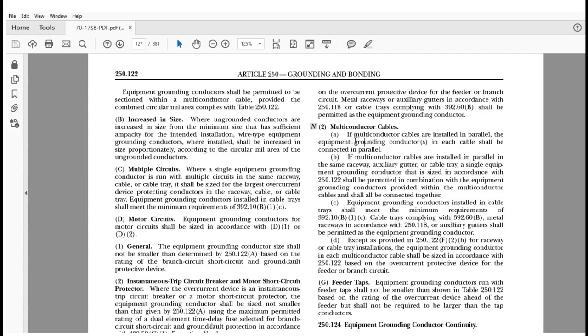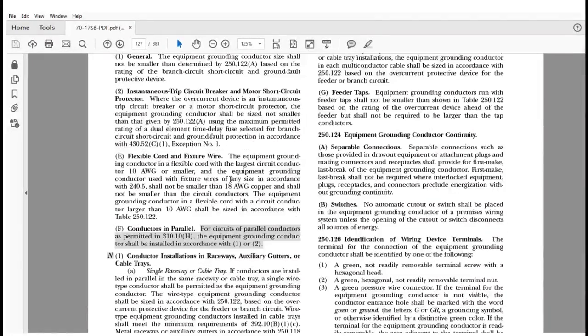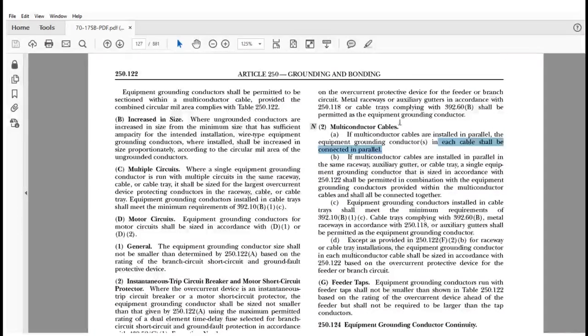It says if multi-conductor cables are installed in parallel, as they're permitted to do, the equipment grounding conductor in each cable shall be connected in parallel. Again, once you get to that location, you bring them together. They have to meet the parallel requirements that we saw previously, the base rule in 310.10(H). So that's nothing new for that aspect of it. Now B comes into play. It says if the multi-conductor cables are installed in parallel in the same raceway.